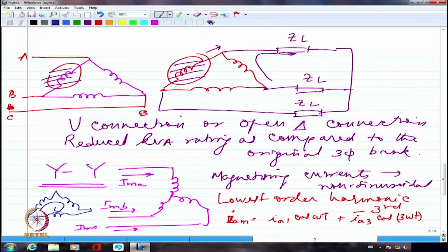The third harmonic current being cophasal, IA3, IB3 and IC3 are exactly of same magnitude, exactly in phase with each other. So it would be able to simply circulate itself through a delta. So I don't have to use the tertiary for anything, just for circulating the third harmonic current, which will restore the balance. Right? Thank you.